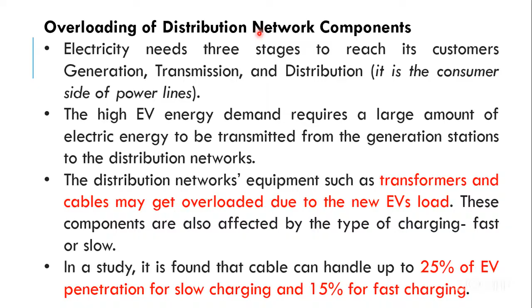Where does it end when we look at our aspect? If you remember the diagram I showed, since you are all electrical engineers, many of you teaching in the field also know that at the distribution level, we rely on our local transformer. The local distribution transformer in our community has already been designed for a certain amount of load. When the loads keep increasing, or when a number of vehicles are connected at a time, the demand will definitely increase, so it will overload the transformers also. A study says that transformer cables can handle up to 25% EV penetration for slow charging and only 15% for fast charging, which means it will create an impact on the transformers too.